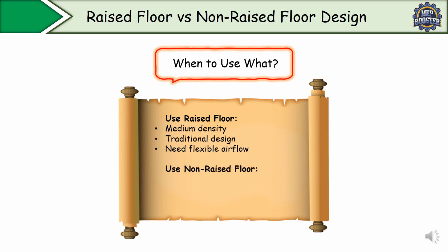Now, where can we use non-raised floor? For high density racks. Okay, suppose you have very high heat load per rack, so you can go for the non-raised floor. Even for moderate data centers, okay, new generation facilities, non-raised floor is preferred because the cost is also lower, no height limitation here, and better compatibility with advanced cooling. Okay, so many new data centers are moving away from raised floors.